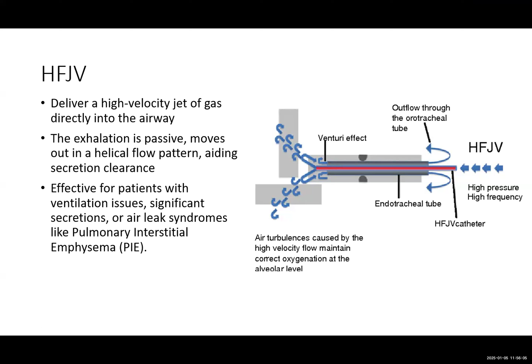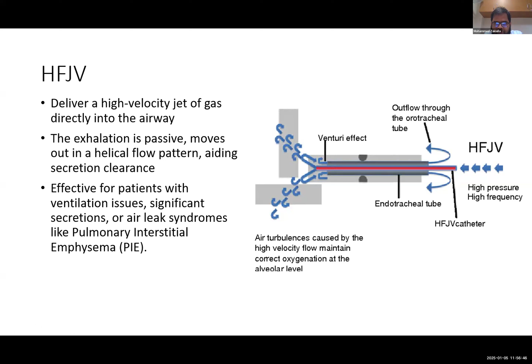So the basic difference, as I discussed, is that exhalation is passive, so it moves in a helical pattern around the inspiratory core of the air. It is basically useful in babies who have a significant air leak, like pulmonary interstitial emphysema. Even compared to high frequency oscillatory ventilation, in babies who are extremely premature, less than 28 weeks, once they have this pulmonary interstitial emphysema air leak, then high frequency jet ventilation is preferred, because it helps in the healing of these air leaks and also in the clearance of secretions. So it has a better effect in babies with significant secretions which require frequent suctioning.